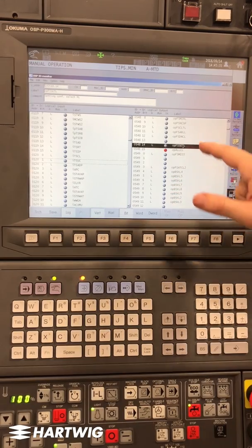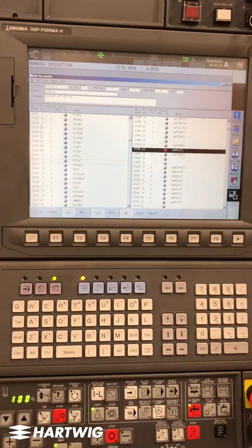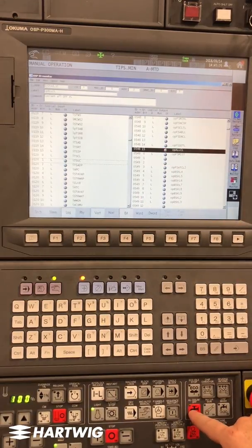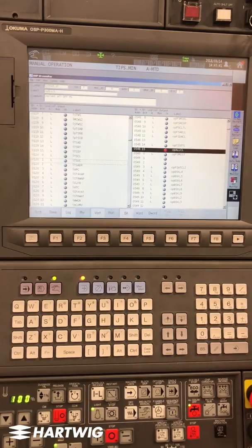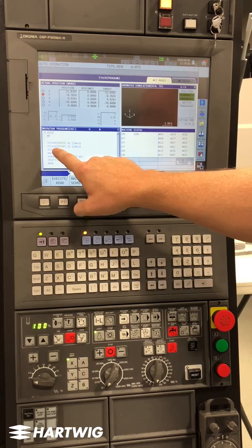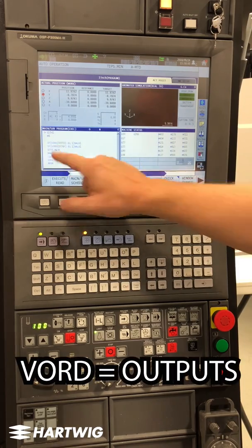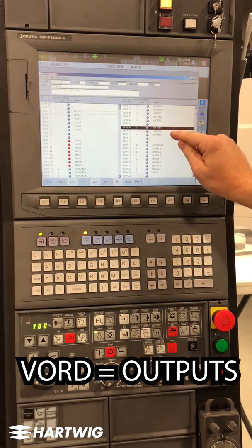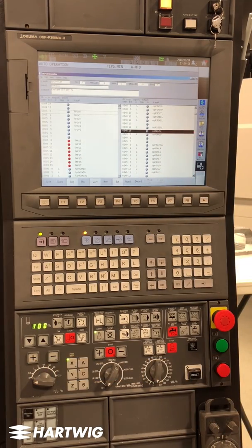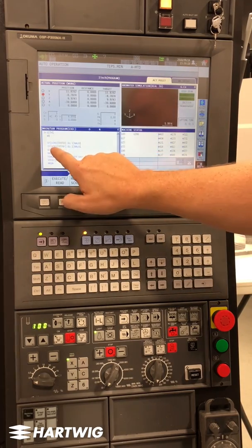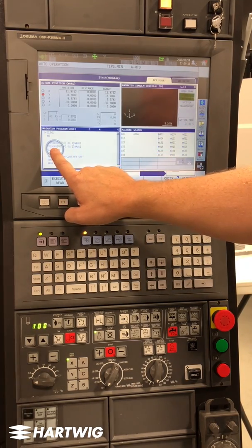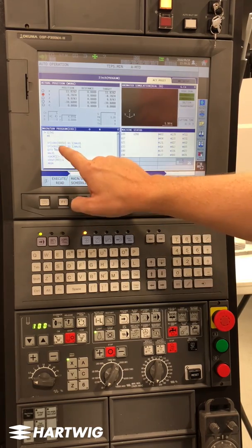What we're going to do is find that specific output and read it, monitoring its state from inside a part program, and trigger an alarm if it's in the wrong condition. VORD. The one we're referencing specifically is the all coolant off button. We want to be sure that coolant is running with this program.